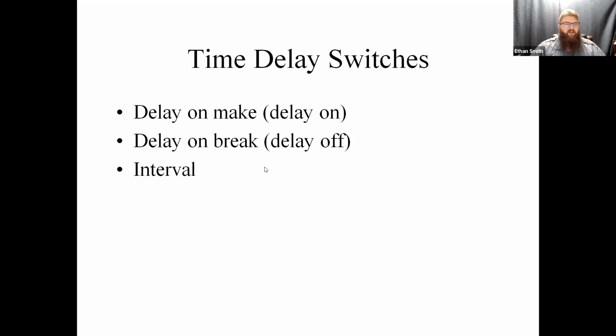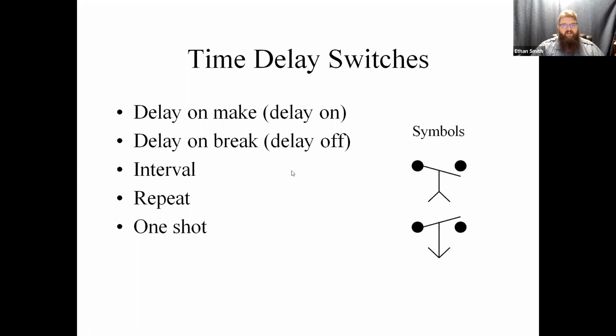Or you can also have interval switches. So we have things like defrost timers would be an interval type switch. Repeat switches would be like interlocks. And again, defrost timers would be something like that always hits at a certain time. I've never seen a one-shot time delay switch used in an air conditioning heating system. That's more of a microelectronics thing. Okay, but in the end, guys, these are all switches. So time delays are typically pictured as an arrow. So this would be a delay on make down below, and this would be a delay on break. Okay.